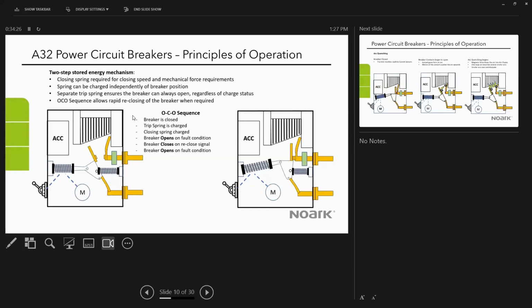And then the sequence of operation is what allows the breaker to very quickly close and reclose whenever it's required. So the sequence starts with the breaker closed. The trip spring is charged. The closing spring is charged. So that's sort of the starting point for this sequence. If the breaker opens on a fault and then gets a reclose signal, it will attempt to close again because the springs are available. But then the breaker can open on a fault condition again. And so the springs are always charged in the right sequence to allow that breaker to reliably open on a fault condition.